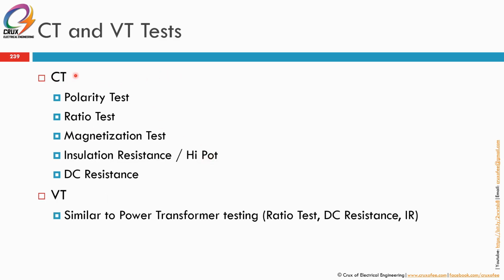CT and VT tests. For CT there are 5 tests, actually 6, so here 6 tests. The CT tests are polarity test, ratio test, magnetization test, insulation resistance, AC high pot, which is for high voltage CTs, and also the CT DC winding resistance. For VT, the tests are similar to the power transformer testing: ratio test, DC resistance, and insulation resistance test. If it's high voltage, we'll also include the high voltage test in the VT testing.